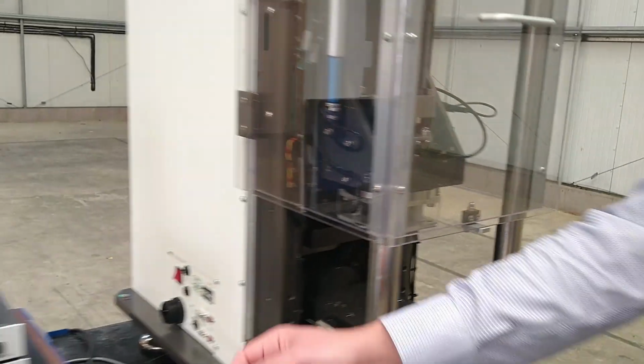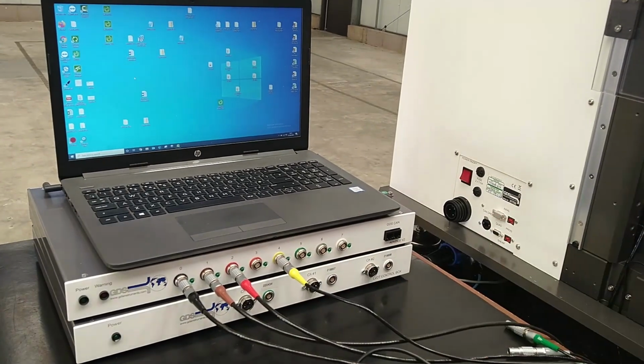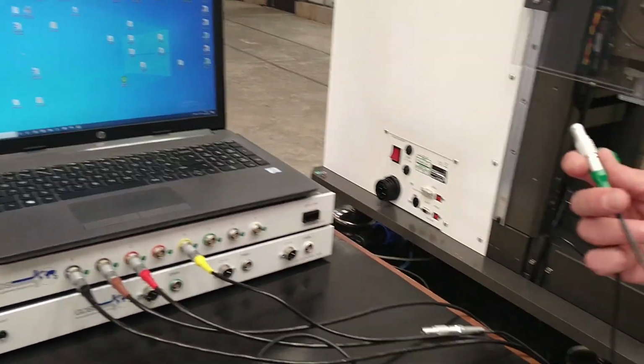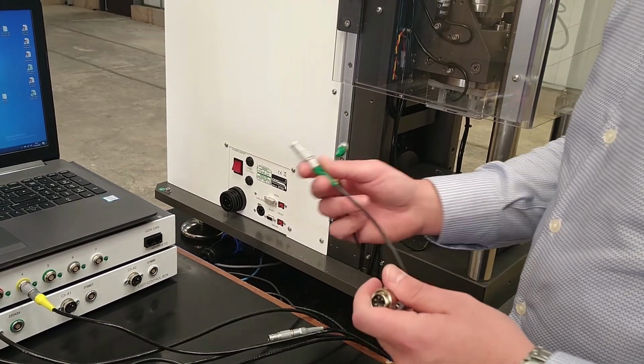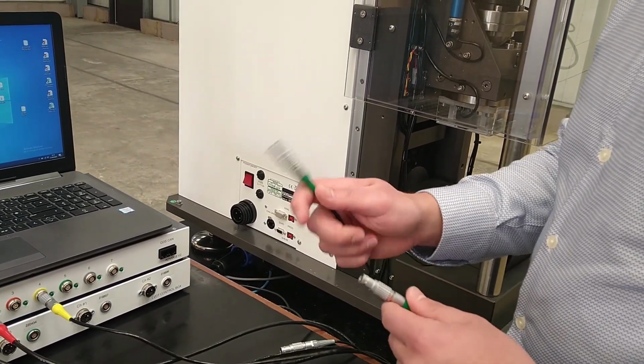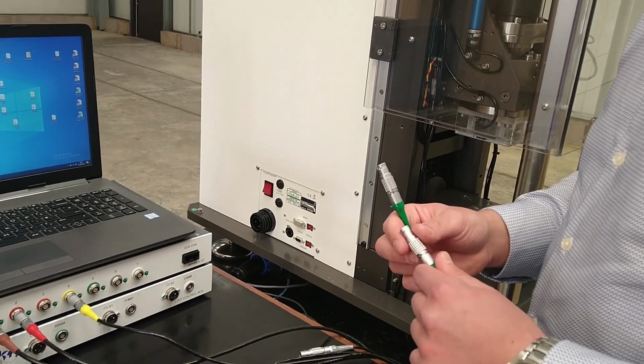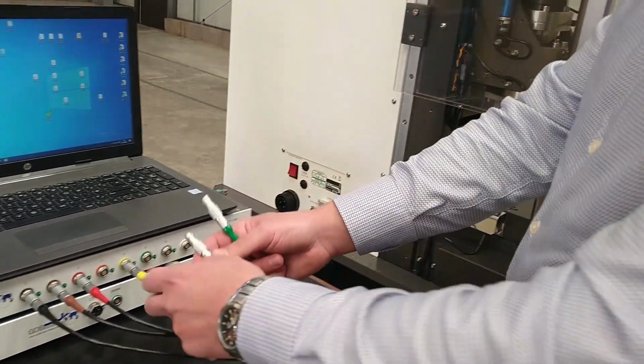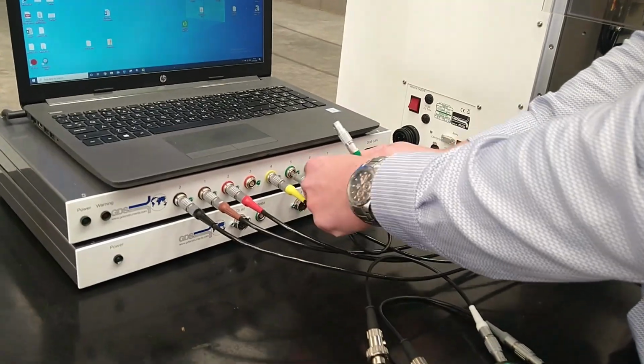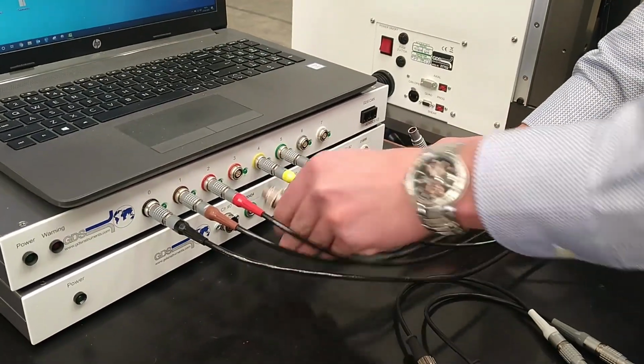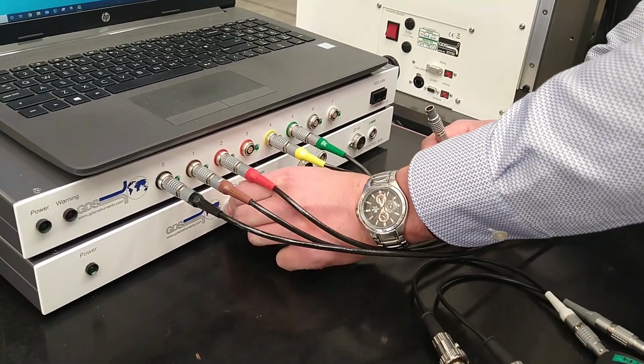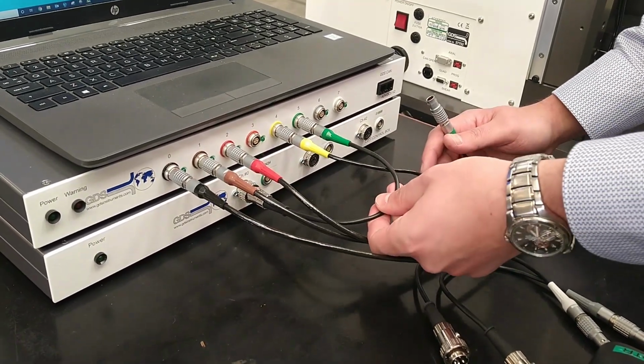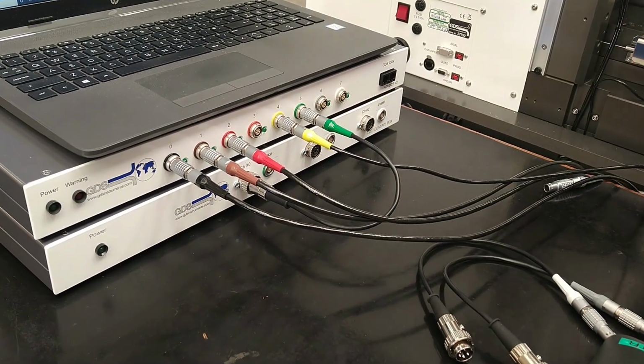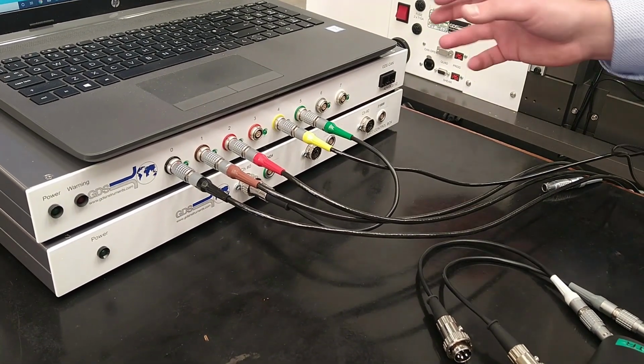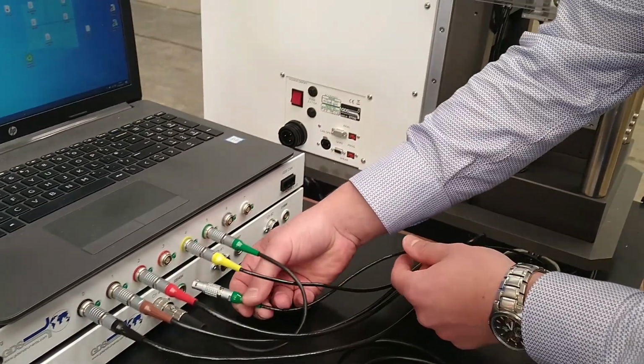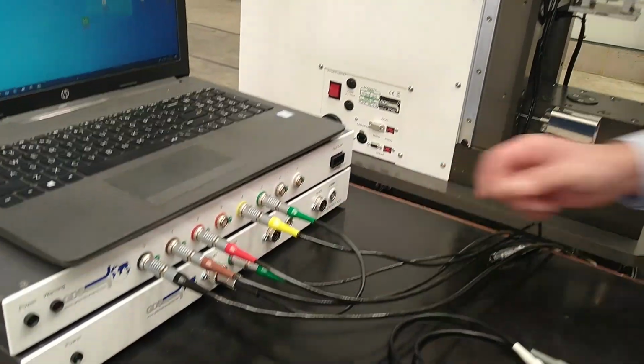And this one will be with the green sleeve, but because that's an LVDT, it needs to go through the additional LVDT box, which contains the amplifiers and signal conditioning for the LVDTs. That's why we have the additional cable, which will plug to the channel number 5 and then to the LVDT box. So it's just a short connection cable, making sure that the AC current is changed into DC current for the box to measure it, and then the LVDT itself connects directly to the LVDT box.